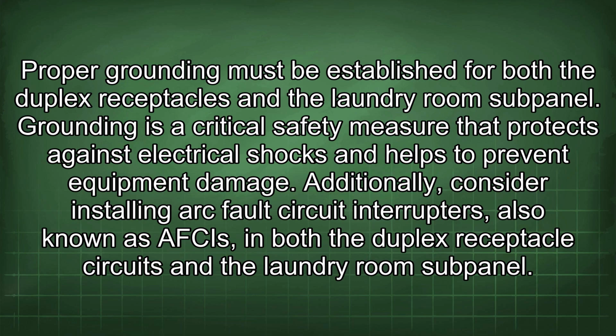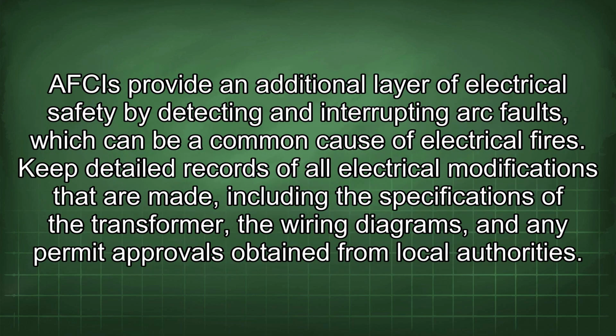Additionally, consider installing arc fault circuit interrupters, also known as AFCIs, in both the duplex receptacle circuits and the laundry room subpanel. AFCIs provide an additional layer of electrical safety by detecting and interrupting arc faults, which can be a common cause of electrical fires.